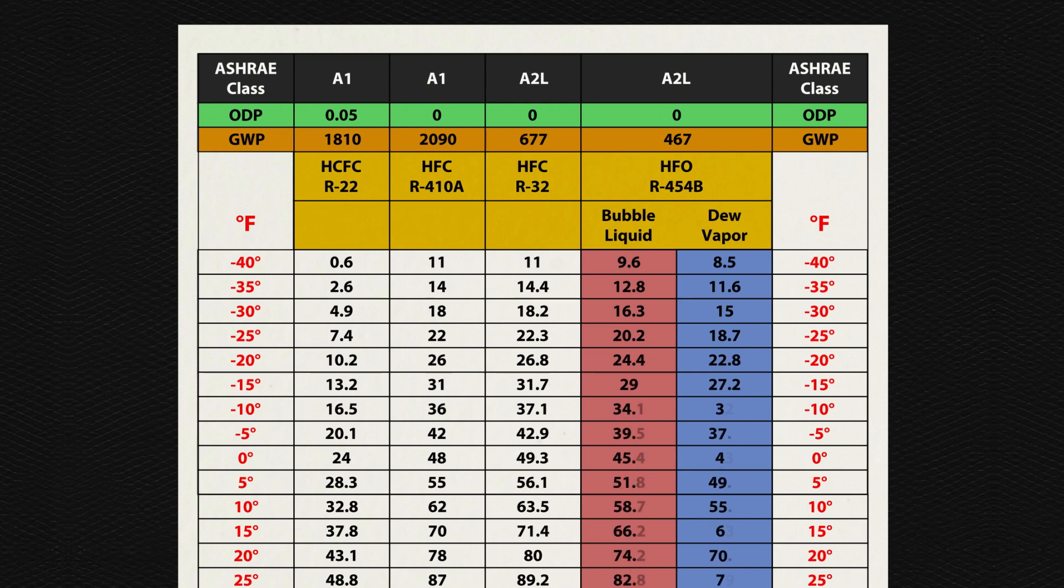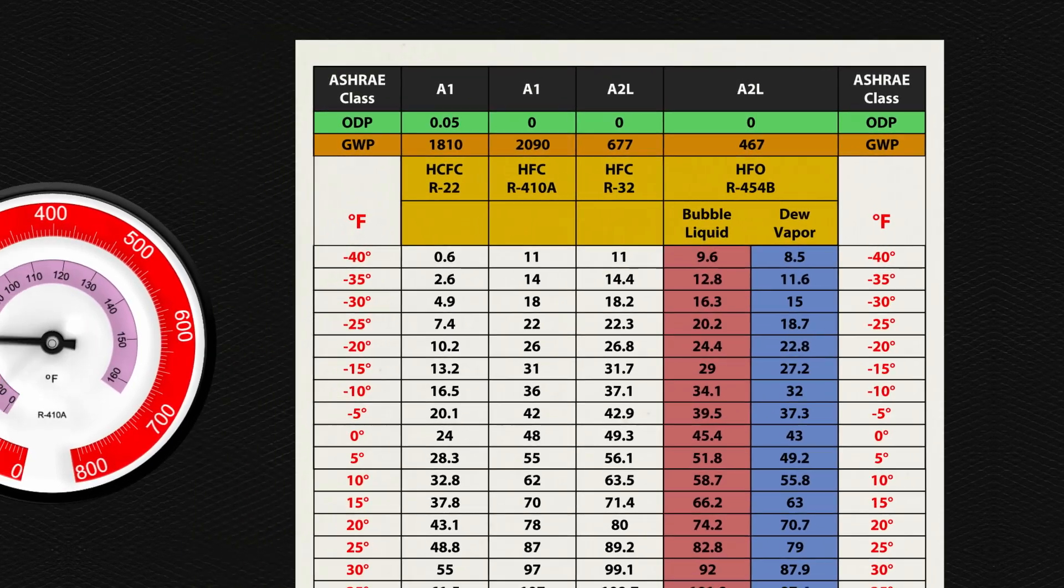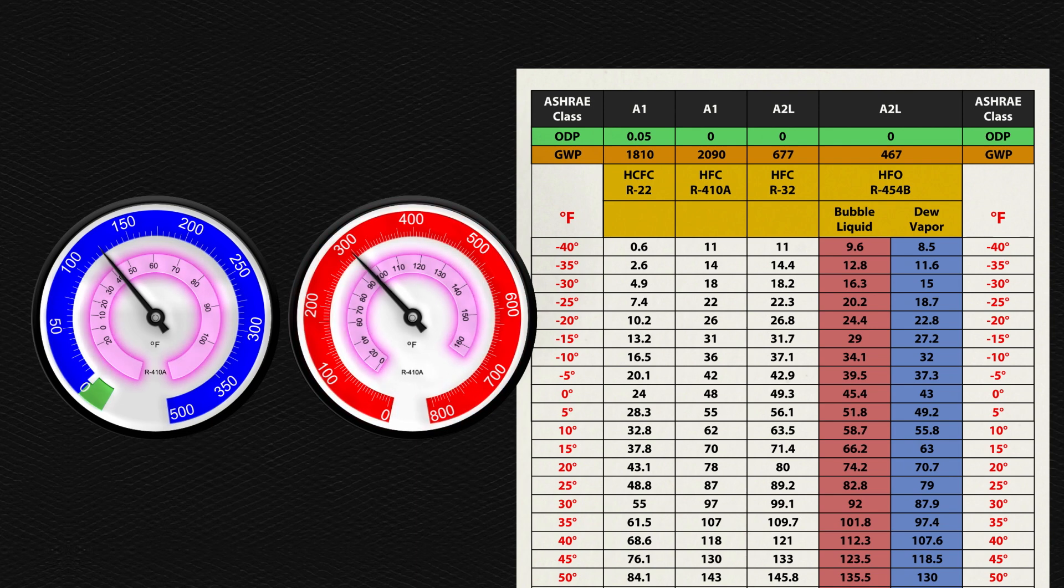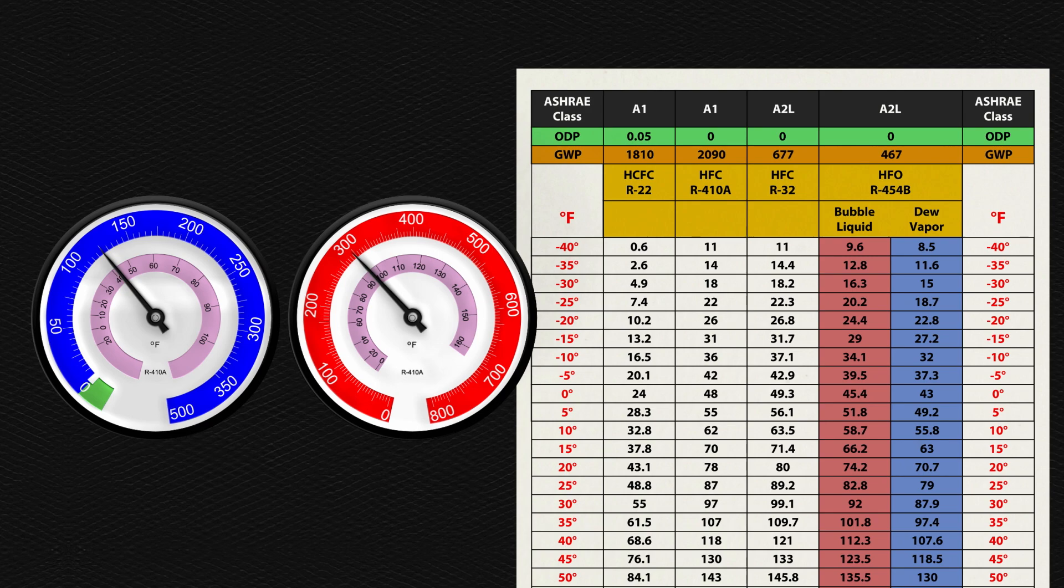The PT chart will be integrated into the technician's instruments. Analog gauges will have the pressure on the outer rim and the saturated temperature on the inner rims. Analog gauges have limitations with refrigerant type and accuracy.